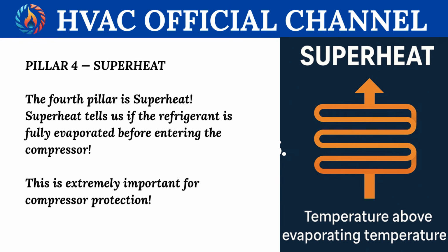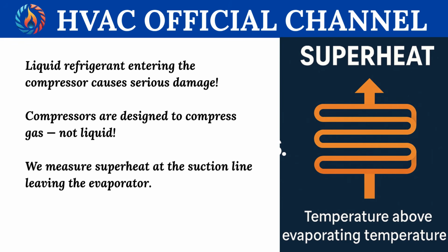The fourth pillar is superheat. Superheat tells us if the refrigerant is fully evaporated before entering the compressor. This is extremely important for compressor protection. Liquid refrigerant entering the compressor causes serious damage. Compressors are designed to compress gas, not liquid. We measure superheat at the suction line, leaving the evaporator.